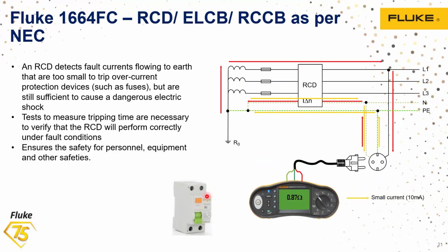Now, whether this tripping happens when there is a real fault, when a fault current occurs in the system, how do you verify that? With the help of the multifunction tester, assume it is an AC type A RCD, and maybe a 30 milliampere one. When a 30 milliampere fault current occurs, the RCD has to trip. To verify that the RCD is working fine, you connect a multifunction tester, choose the type of RCD, and select the 30 milliampere current. It injects that current and makes the RCD trip. If the RCD is tripping, it is a clear indication that it is working completely fine. If it is not tripping, that is a real problem.